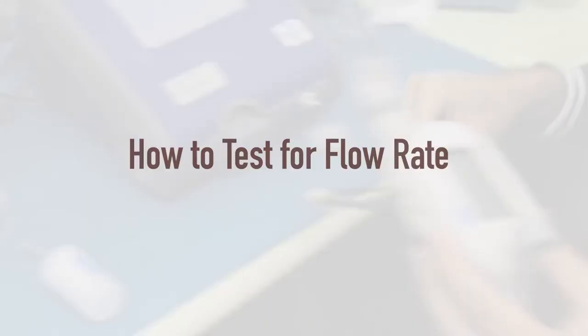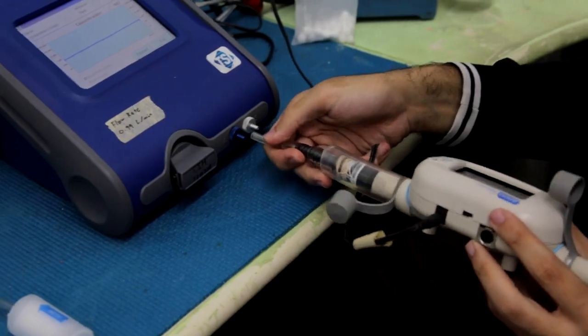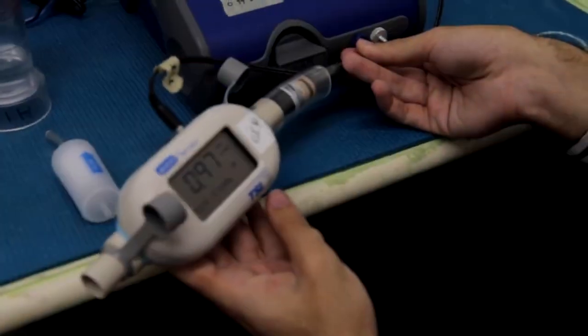To test the PortaCount's flow rate, you want to take a mass flow meter and attach it to the meter's tube into the ambient inlet. Next, your flow meter should then show a reading of your flow rate. You want readings as close to 0.99 as possible on your meter. A reading anywhere from 0.96 to 0.99 is considered satisfactory.